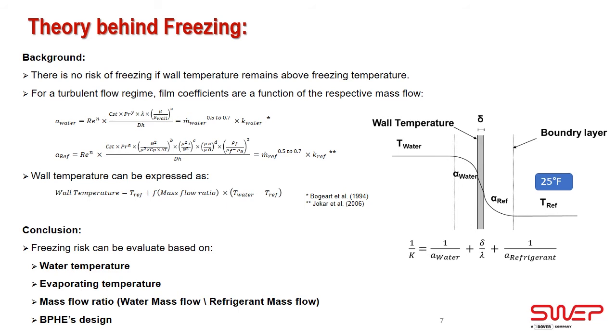It's difficult to say if there is a risk of freezing or not, because what is important in order to evaluate freezing risk is the wall temperature or surface temperature, which you can see on this slide. And the wall temperature is a function of the evaporating temperature, the film coefficient on the refrigerant side, the film coefficient on the water side, and the water temperature as well. We tried to simplify it a little bit, and we ended up with a function which can evaluate the wall temperature based on the water temperature, the refrigerant temperature, and the mass flow ratio. The mass flow ratio is the ratio of the water flow to the refrigerant flow.